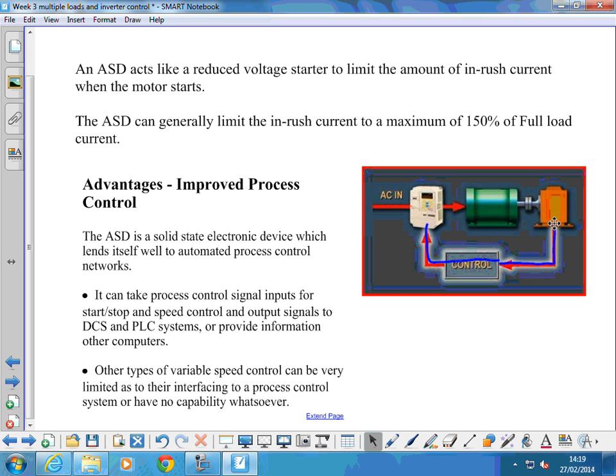Okay. So they're quite closely controllable in that sense. They work well with a range of different sensors to be able to keep the motor at a constant speed or react to changes in the system. We need more flow now, speed the motor up. It'll do that quite well. Other types of variable speed control can be very limited as to their interface into a process control system, or they have no capability whatsoever. So you may be asked to look at some other types of drive system and how they compare with inverter drives of induction motors and so on, depending on the applications you're asked to look at.